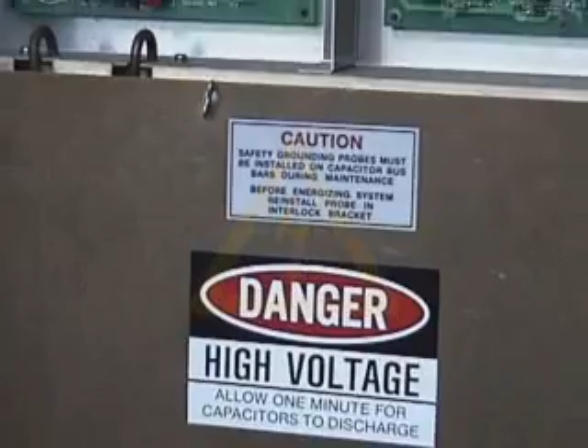Most types of lasers transform less than 1% of the electrical input power into light. As a result, most lasers need very powerful electrical supplies. The CE mark in Europe or the UL mark in the American market on a laser product confirms the electrical safety of a product with respect to its dedicated use. As long as users do not open the power supply and touch the interior parts, they are not at risk. Only competent service personnel should carry out electrical repairs.